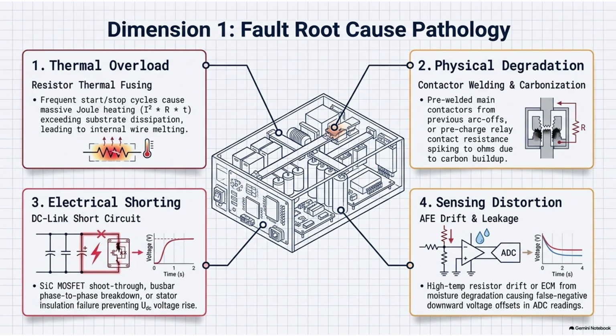As those plates pull apart, that plasma arc melts the surface layer of the contacts. If the metal is molten, and the system tries to close them again quickly, or if the liquid metal pooling is severe enough as they separate, it cools and physically fuses the two sides together. This is pre-welding.